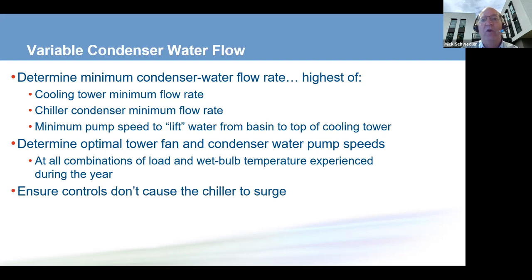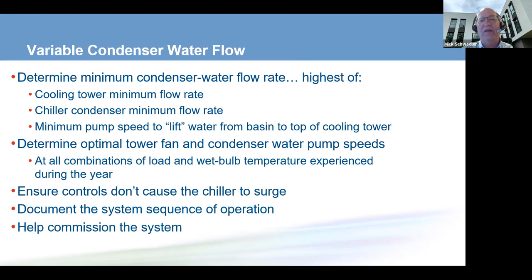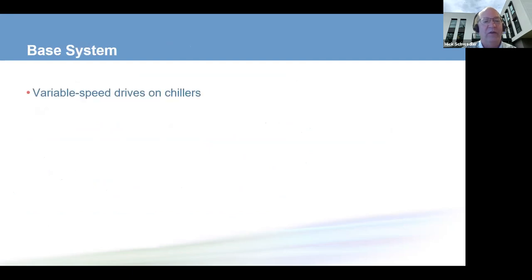The other thing, you have to make sure you don't reduce the condenser water pump flow rate so fast that the chiller goes into a surge region. Because when we reduce the flow rate, the leaving condenser water temperature goes up, and we can get into surge if we still have high wet bulb temperatures. Finally, you want to make sure as an engineer you develop a sequence of operation. You make sure it's commissioned properly, so it can take some time to do this. So is the juice worth the squeeze?